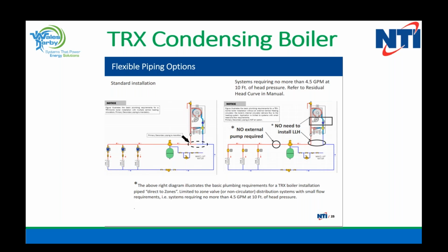If we're going to maintain a 20-degree delta, 4.5 GPM, that's 45,000 BTUs. 10 feet of head is about a 166-foot long loop. So that's still a pretty decent sized home, definitely a condo or a small apartment. But if we go above those GPMs and head, then it must be a standard installation, where you'll see on the left-hand side the closely spaced tees, and that is primary, secondary. If you intend on zoning with circulators, then it definitely has to be in primary, secondary piping.